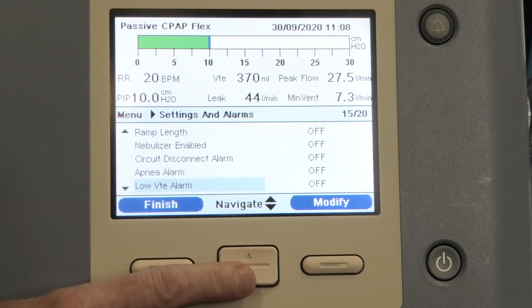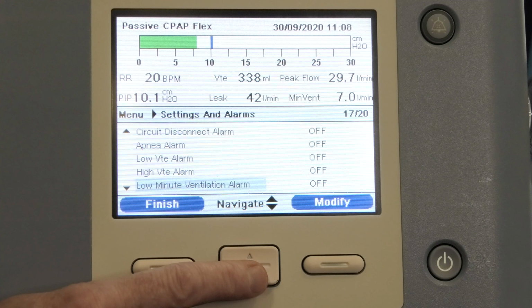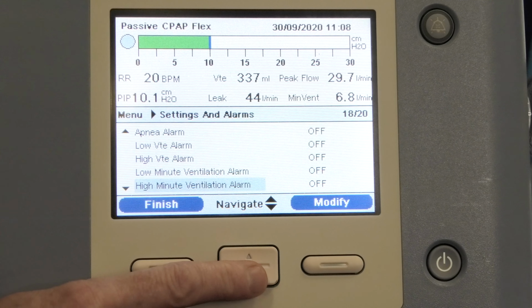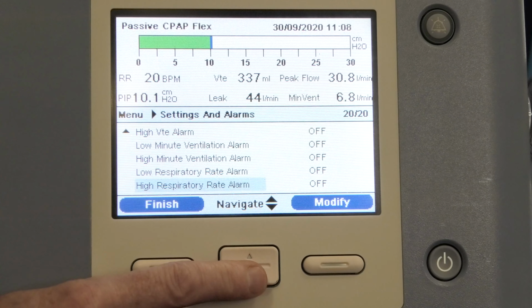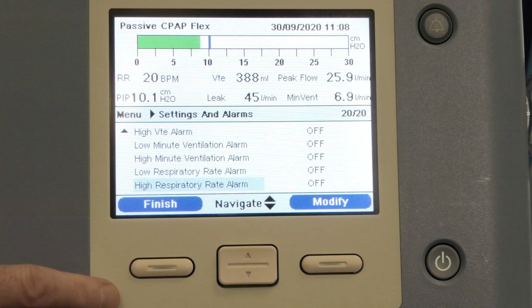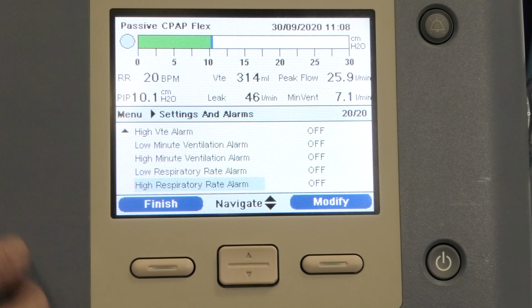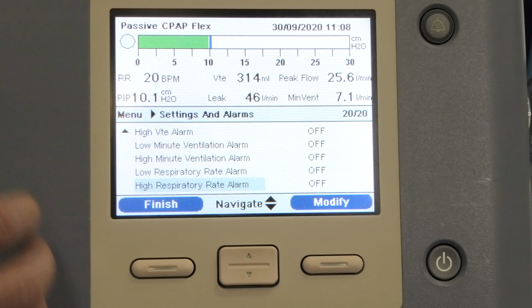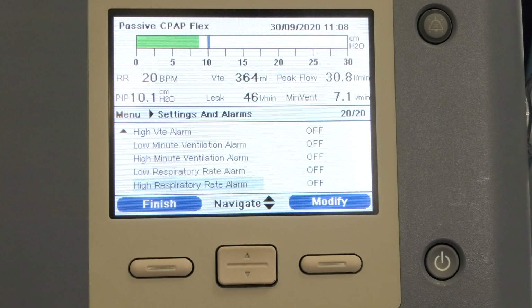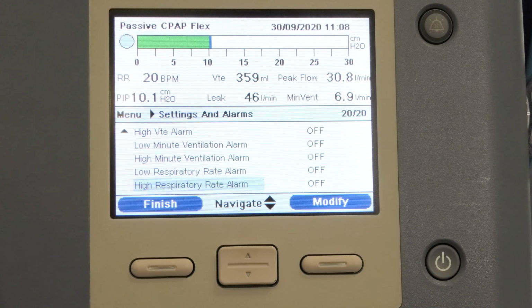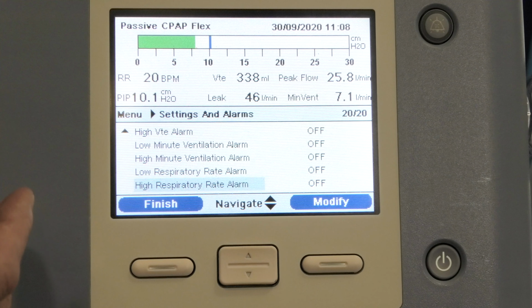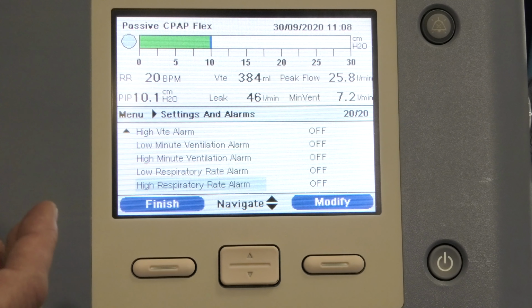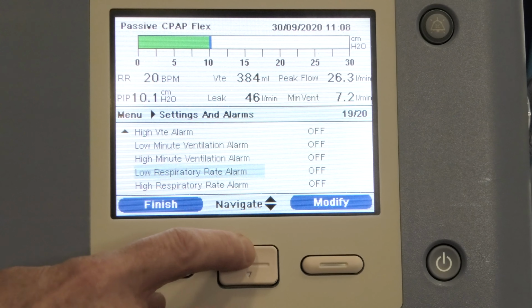We have lots of other alarms: high and low tidal volume, high and low minute ventilation, high and low respiratory rate. We tend not to set them because it makes the machine alarm all the time. We know when the patient is apneic because we've already set an apnea alarm, and we know if the circuit's become disconnected. Those are really the only two alarm settings that we need to set for safety purposes.